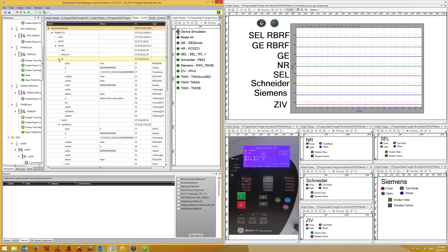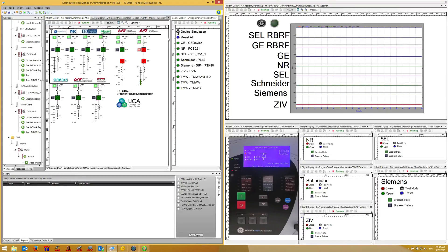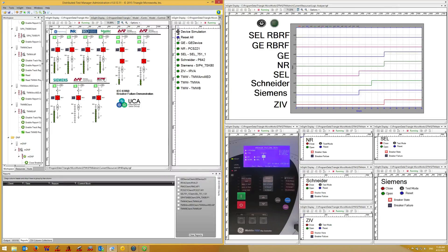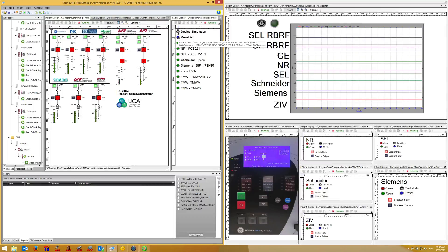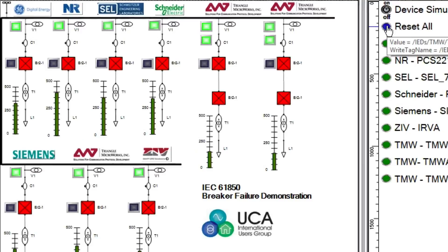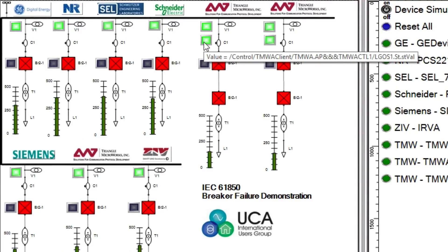The LGOS status value can be tied to a display to indicate the status of a Goose connection. Let's take a look at the single line diagram again. First I'll reset all the breakers just to clear up the display. The LGOS status value can be tied to this display to indicate the status of a Goose connection. Notice if I hover over the indicator, the pop-up help will show the link to the LGOS data. In this demo, the 61850 client simulation in the distributed test manager monitors the LGOS status and displays it on the single line diagram.